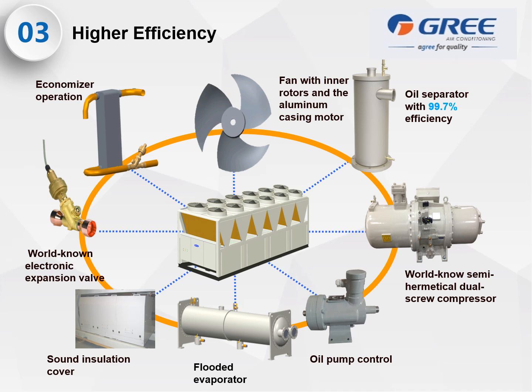Higher efficiency comes from the economizer operation, fan with inner rotors and aluminum casing, and an oil separator with 99.7 efficiency. It has an almost 3,000 steps electronic expansion valve, and uses a semi-hermetic dual screw compressor and oil pump control. A flooded evaporator means better efficiency of the product. It has a sound insulation cover, and if you need better sound insulation, you can request it via the GREE factory.